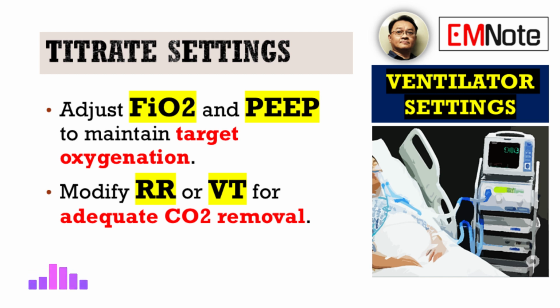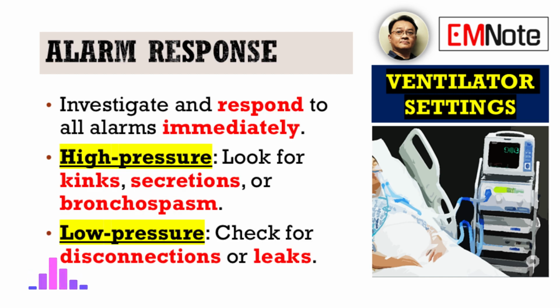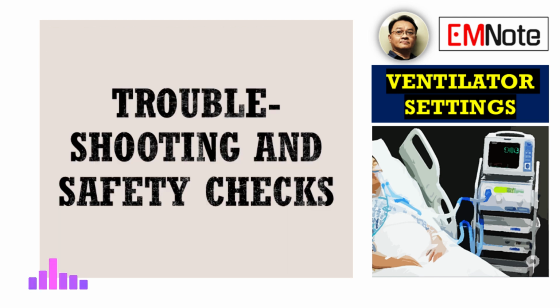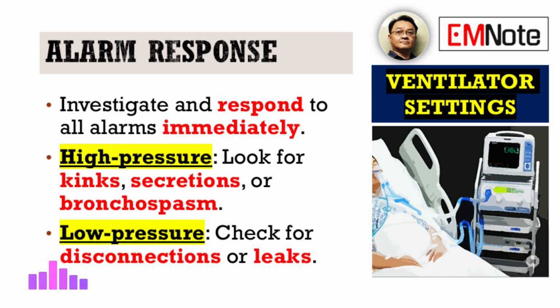Okay, alarms. They can definitely be alarming, and they demand immediate, decisive attention. What are the key alarms we need to watch for, and how do we react to them quickly and effectively to ensure patient safety? Yeah, this brings up a critical point about rapid response. Ventilator alarms are not nuisances to be silenced. They are urgent safety signals. Prompt, accurate investigation and intervention are paramount. Ignoring them, even for a moment, can lead to severe patient harm, or worse.